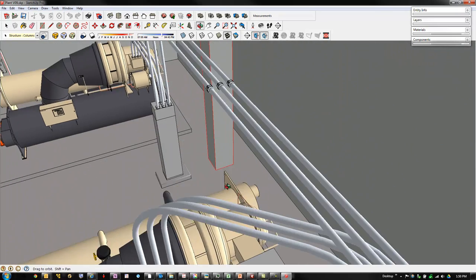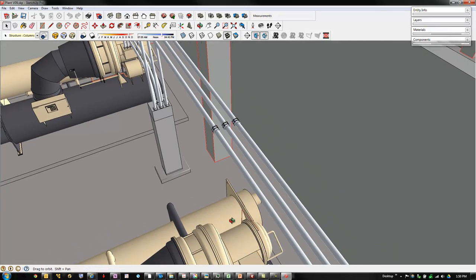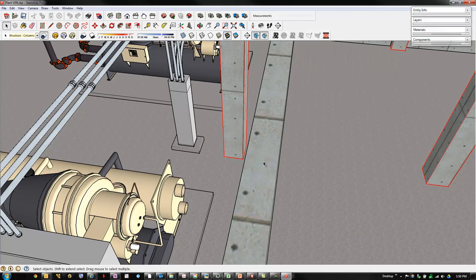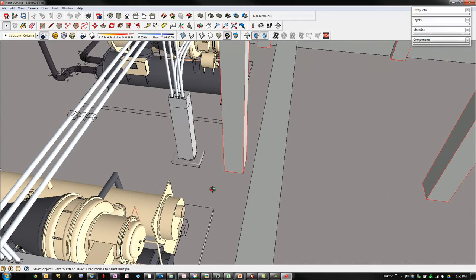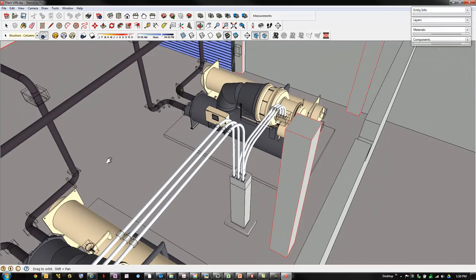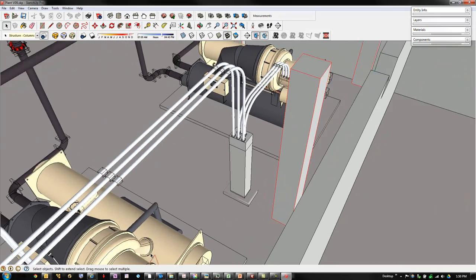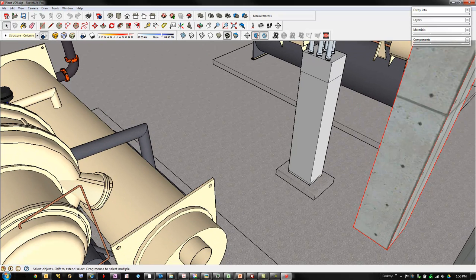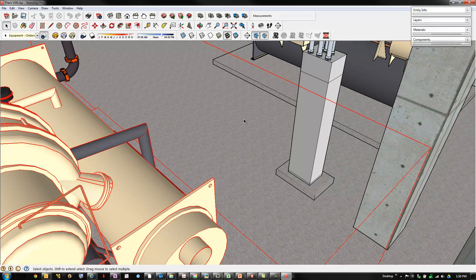And then if we look at it from above and turn around a little bit, or you walked around to the other side, you could see this too. But what I'm trying to show you is, without getting myself inside the wall, right here there's a connection that comes off that second stage of the compressor and goes into this thing. Well, that's probably the hot gas coming off the compressor, which would mean this is the condenser.